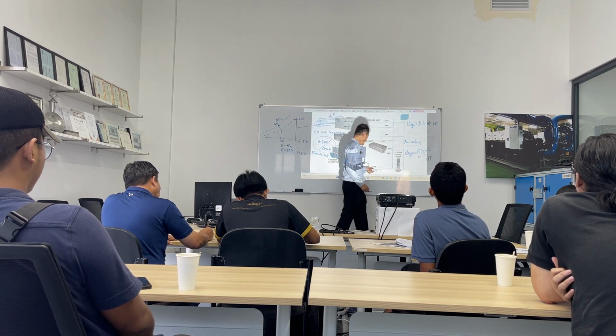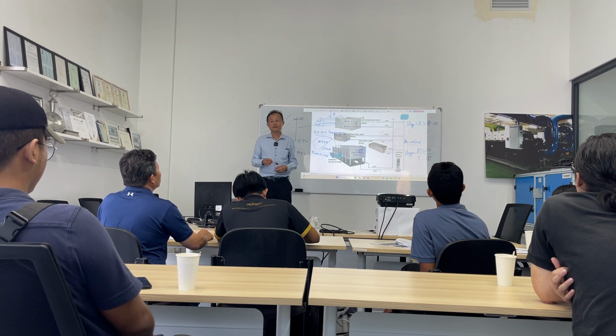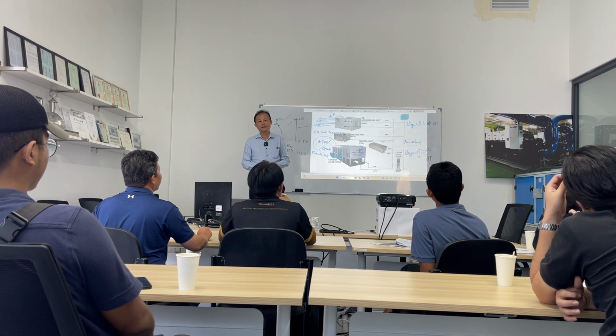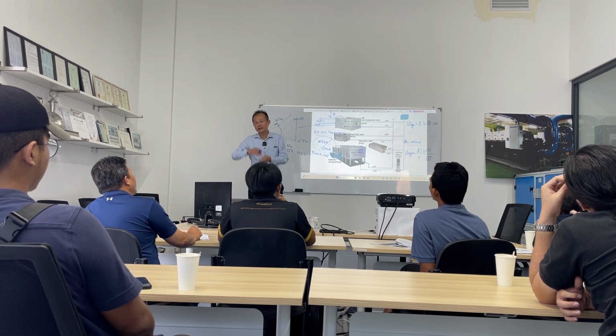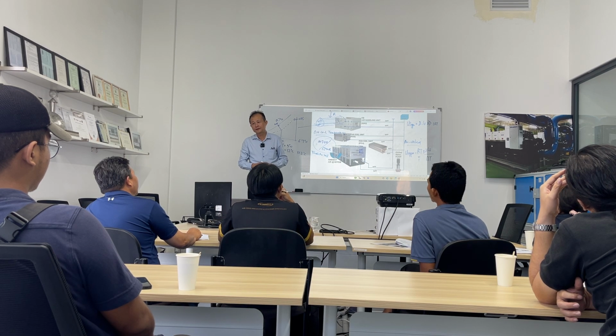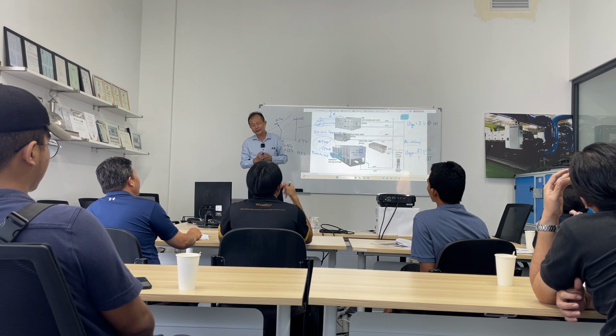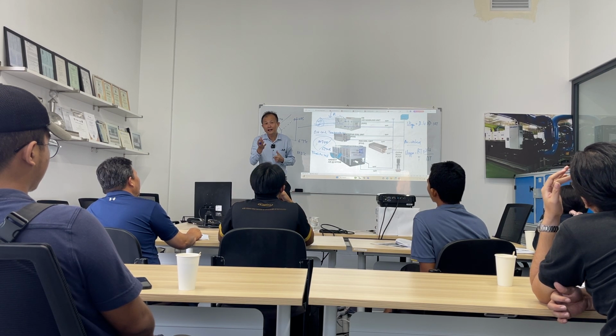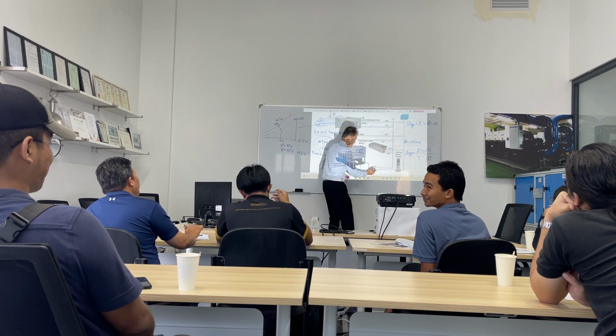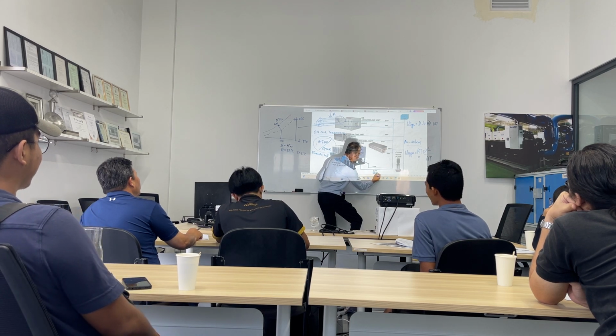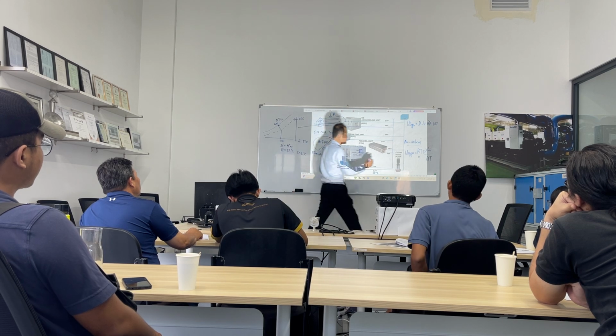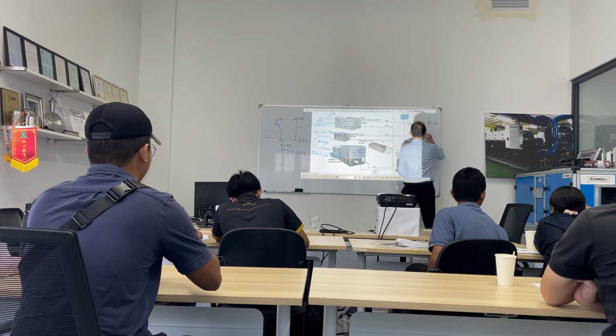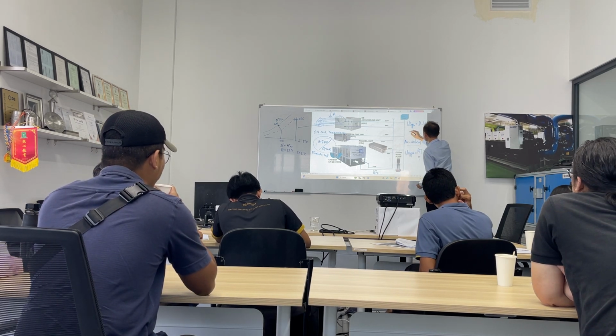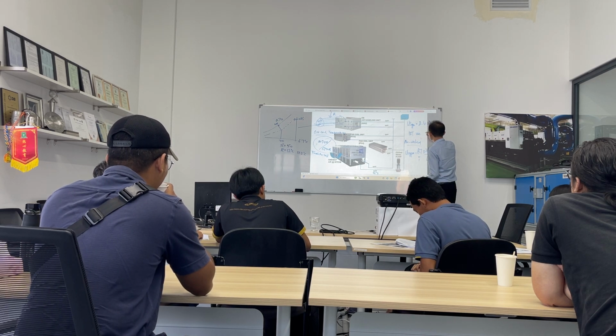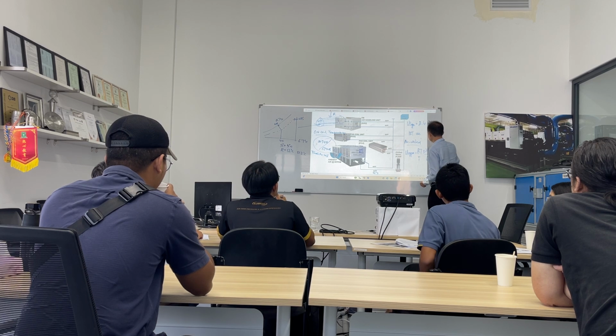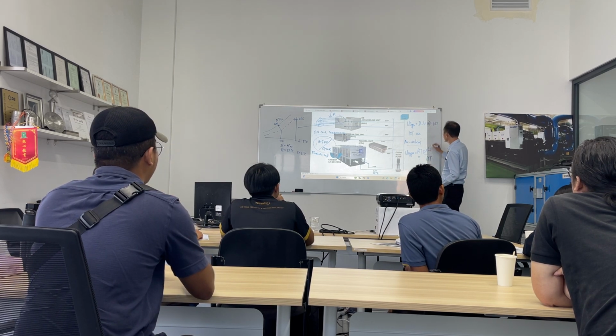If I increase the delta T here, what do you think the impact on the US GPM is, increase or decrease? Decrease. Okay. Let's say I use 56 for example, right now. So for one ton I need to use lower flow: 24 divided by 12 is 2 US GPM.